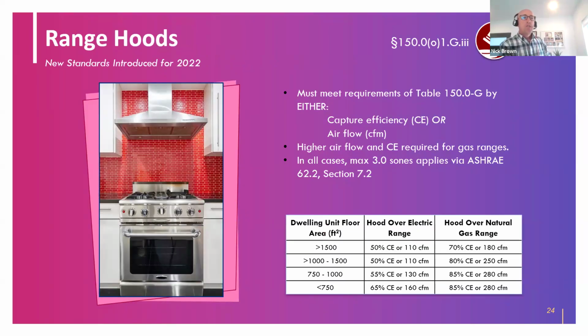Range hoods now differentiate between gas cooktops and electric, and more airflow from the range hoods is required when they're placed over natural gas ranges, because those gas ranges create additional pollutants that electric ranges do not. Now, you still need a range hood over electric cooktops and induction cooktops, because you're creating moisture, you're creating cooking byproducts that need to be evacuated from the space. So don't think there's no range hood required with induction. There is, but there's higher airflow, bigger range hoods required if you put in a gas cooking system.